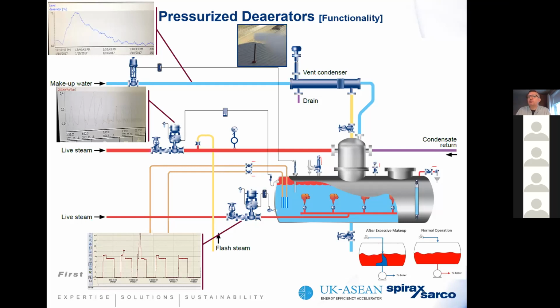Look at your steam profile. So look at, if there's a steam meter serving the deaerator, look at the profile, because you can see with the trend from this customer is very much on off. And in this case, we found that each time the deaerator filled with makeup water, the second boiler had to start to maintain the steam demand, which is the total steam demand of the system. In reality, it was firing just to satisfy the deaerator, because you could see in this case, the deaerator steam demand went up to 8 ton instantaneously, held for a certain period of time and dropped off again. So very much on off.